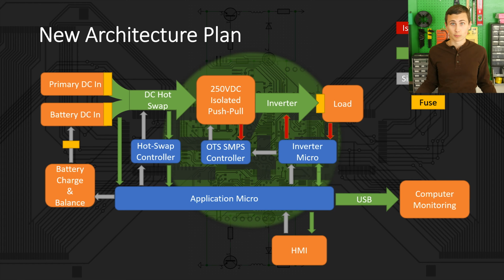Should the low-level micro lose its brains, the high-level micro is also monitoring temperature and expects a periodic ping from the low-level micro. Should this ping ever not occur, the high-level micro is able to pull the plug for that main DC boost converter and then hold the low-level micro in reset. This combination effectively disables the power stage of the UPS and makes sure that everything's safe. This will occur if a ping is ever missed or if the high-level micro detects a thermal runaway condition that the low-level micro didn't catch. The high-level micro also handles charging and cell balancing for the auxiliary DC source. We assume that these batteries will be 2 series 12-volt lead-acid batteries, which are unvented, sealed batteries.